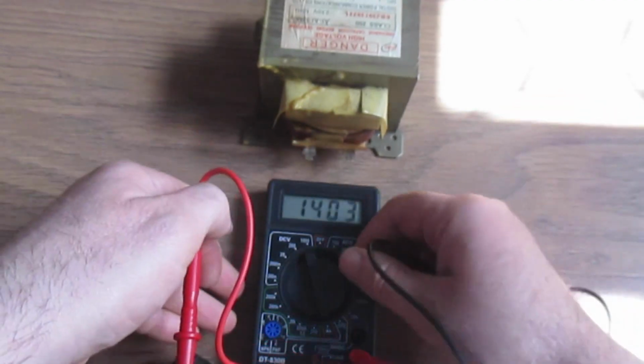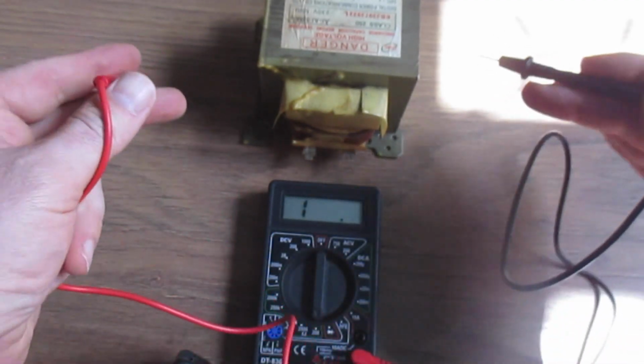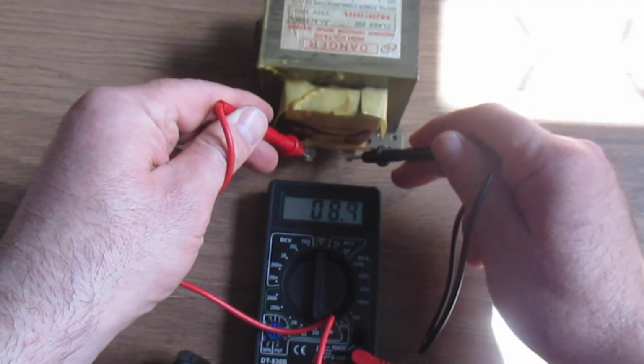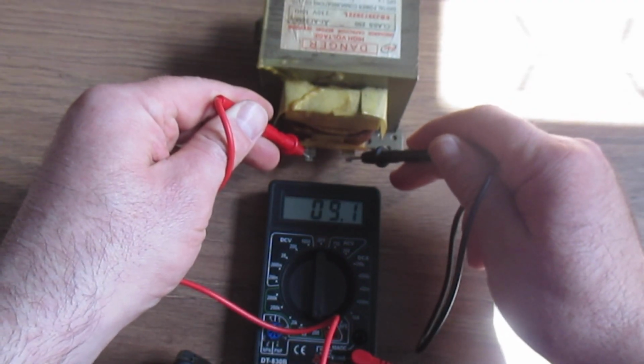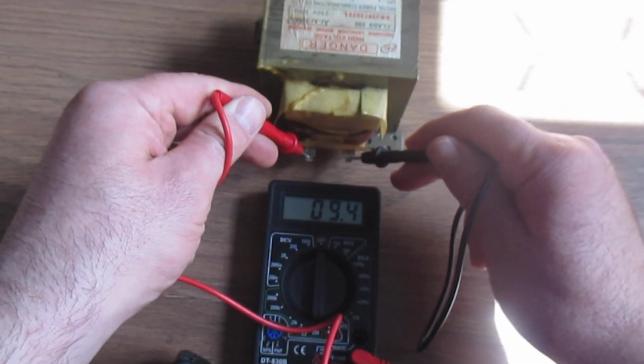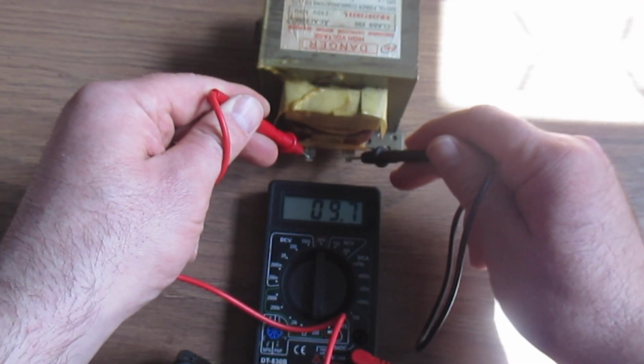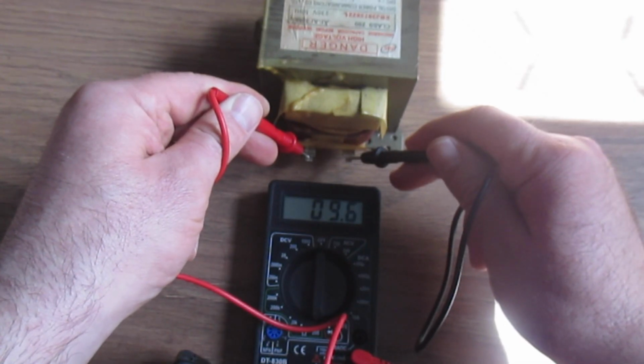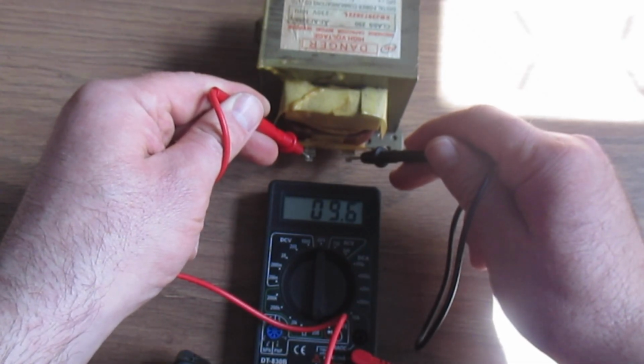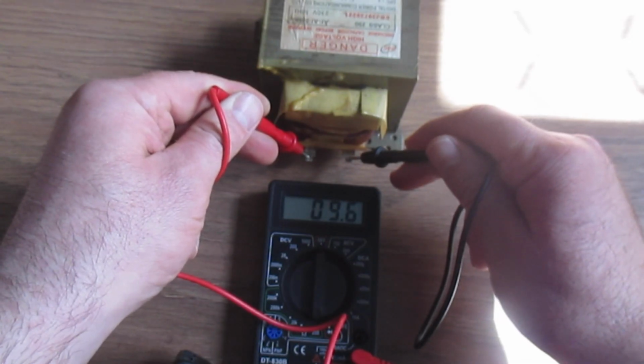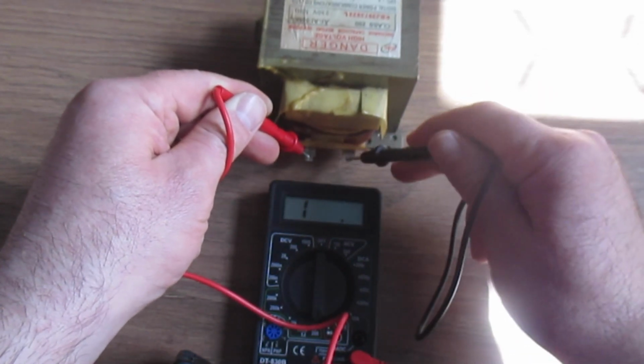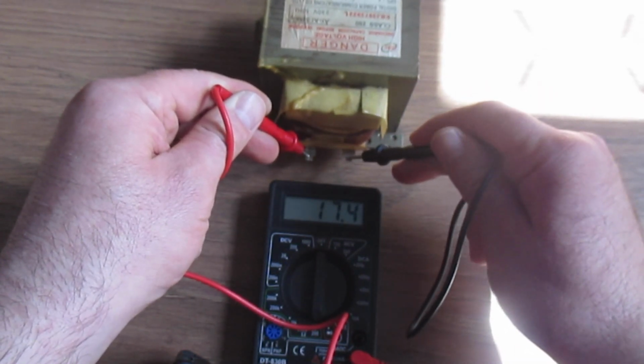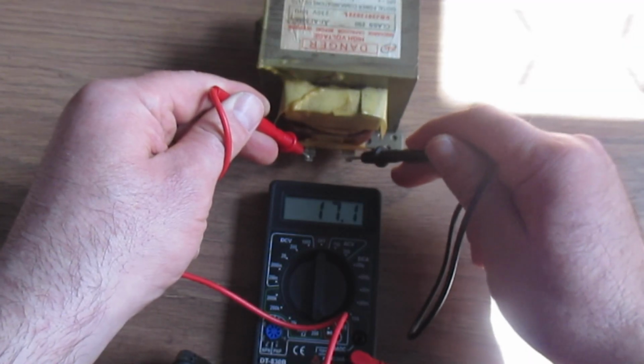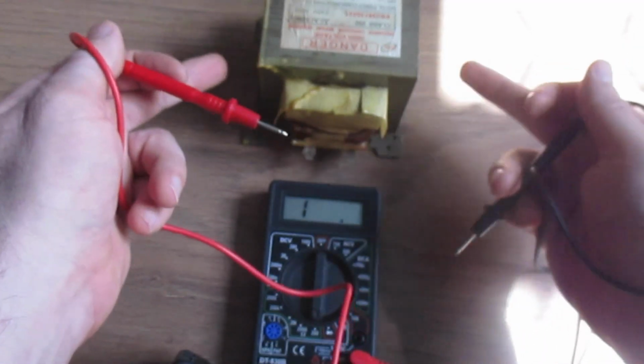Next, we set the resistance to 200 ohms. We test and see that the readings vary from 8 to 17 ohms. The values begin to jump to 20 to 30 ohms. Then the value returns to a normal 3.5 ohms. The resistance should be between 2 and 5 ohms and be stable. This means the primary winding is faulty, which means the entire transformer is faulty. The transformer needs to be replaced.